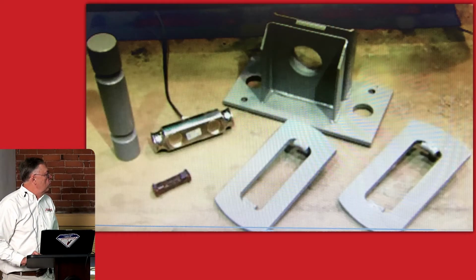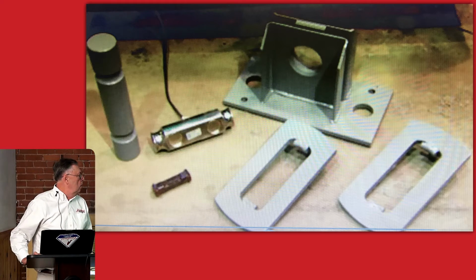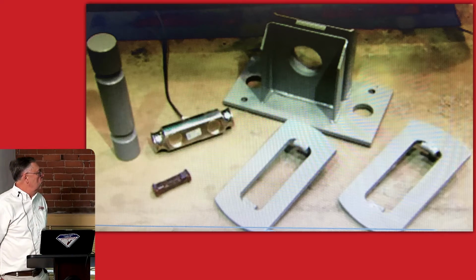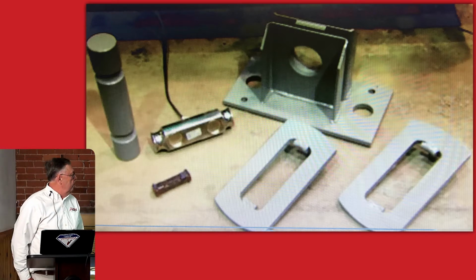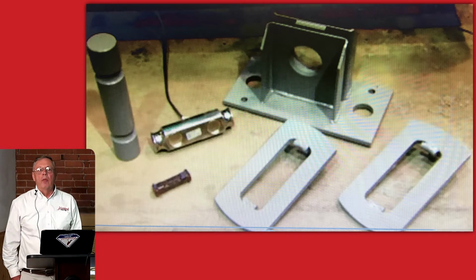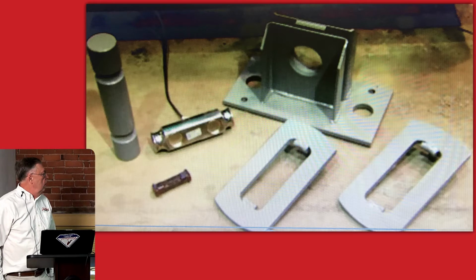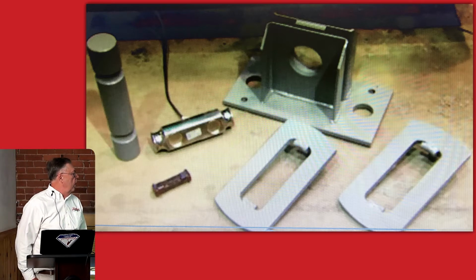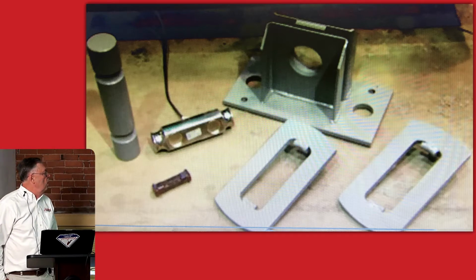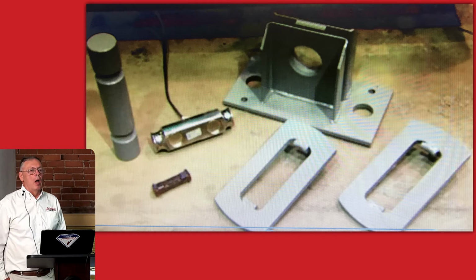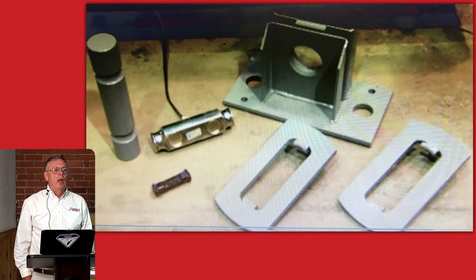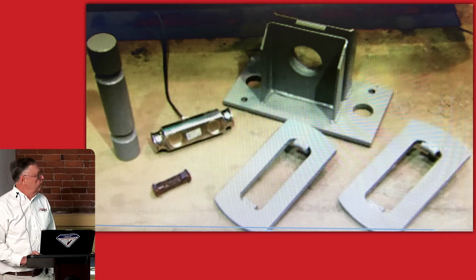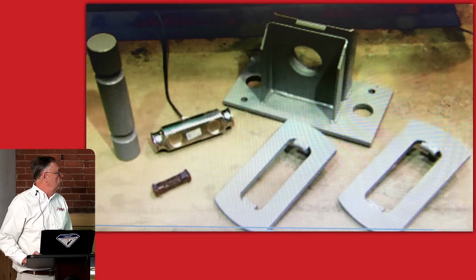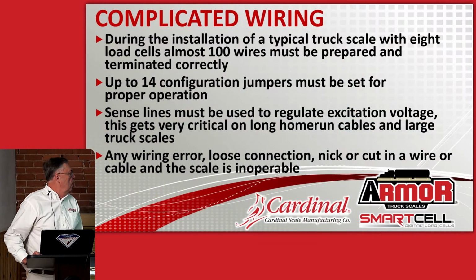This is pretty much what a typical truck scale suspension system looks like. You've got a corner stand with a bearing in it. You've got a pivot that sits on top of that, a double-ended beam load cell, a pair of suspension links with wear points, and then a load bar at the bottom. A lot of parts to assemble and a lot of parts to keep running correctly. So that's kind of an issue that's been out there for a long time.